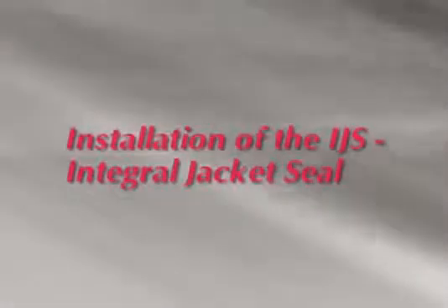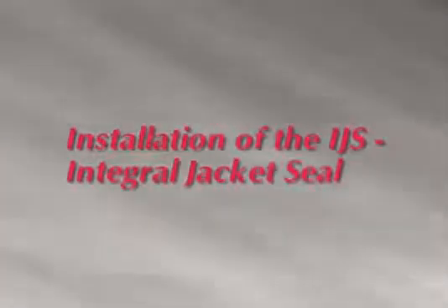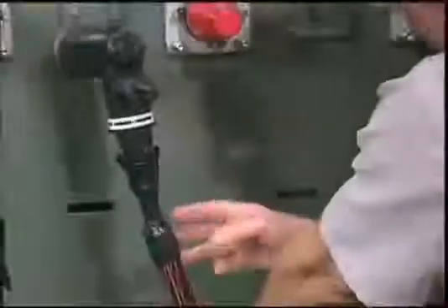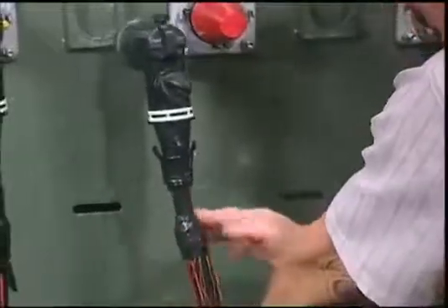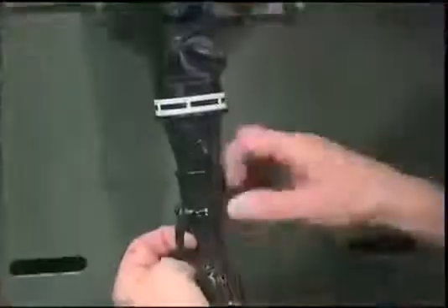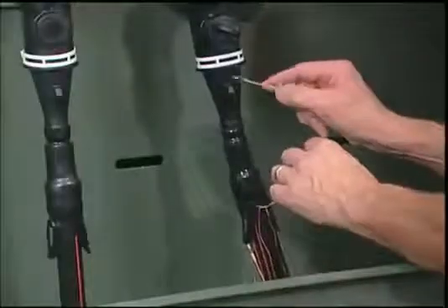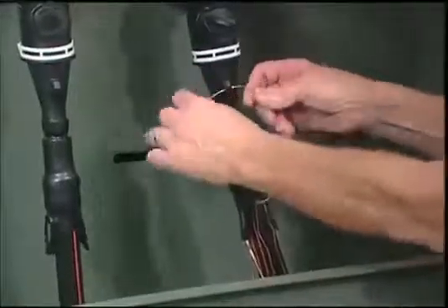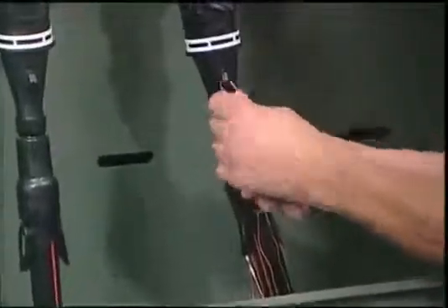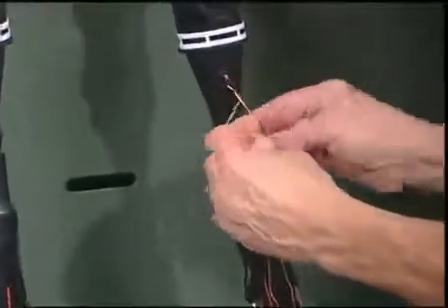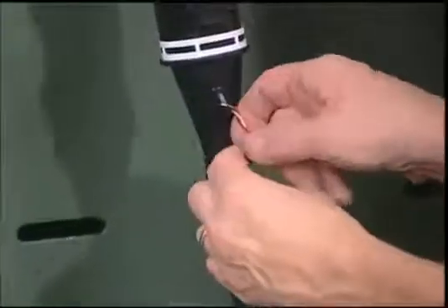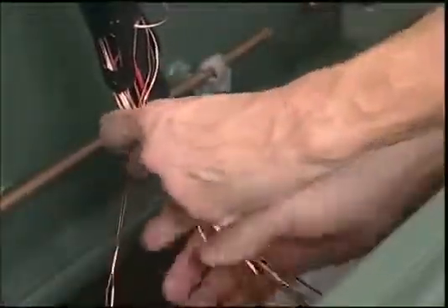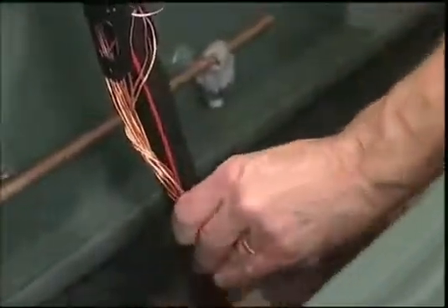Next, we'll complete the installation of the IJS, the integral jacket seal. First, apply a thin layer of silicone grease over the PVC. Then pull the integral jacket seal down as far as it will go. Next, attach one of the wires to the grounding tab on the elbow. Then twist the remaining concentric neutral wires in preparation for connection to the system ground.